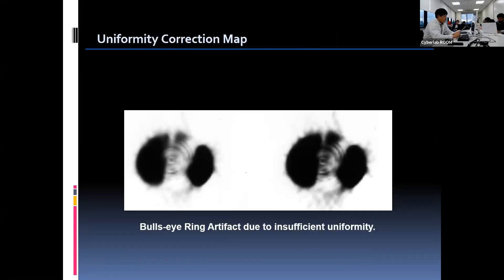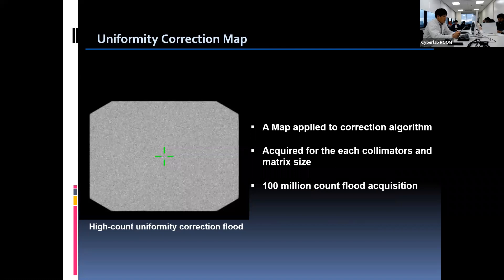This image shows the bullseye ring artifact in the SPECT image due to non-uniformity. Non-uniformity across the field of view must be corrected for both planar and tomographic image quality. Especially in tomographic imaging, small variations in uniformity are multiplied by the number of projections, causing artifacts in the reconstructed image. To solve this, a high-count uniformity correction map should be acquired and stored. The uniformity correction flood is then used as a map applied to the correction algorithm for every pixel in the image.